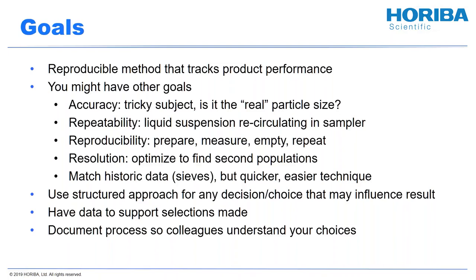You might have some other goals: accuracy — is it the real particle size, which is generally a question of definition; repeatability — can you get the same answer twice from the same exact sample; reproducibility — can you get the same answer twice from two samples off the same batch; resolution — can you see changes that are important to you. You'll also want to use a structured approach. If you develop a method and three years later questions come up, you want to be able to find that dusty notebook and tell people exactly why you picked what you picked. Document the process so your colleagues and yourself understand your choices, and so that if your particles change a little bit, you can make intelligent guesses about how to update your methods.